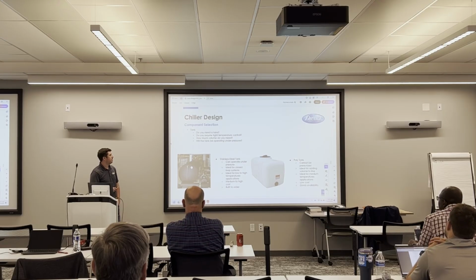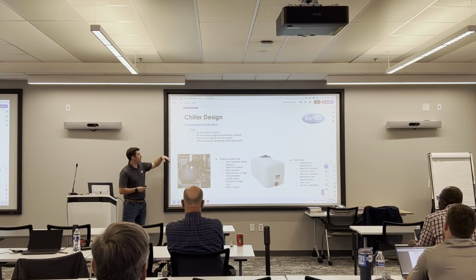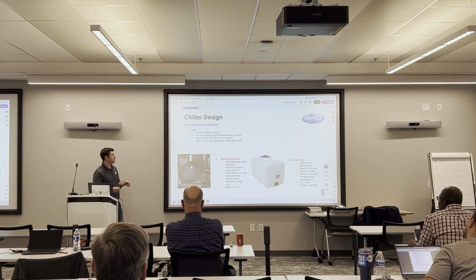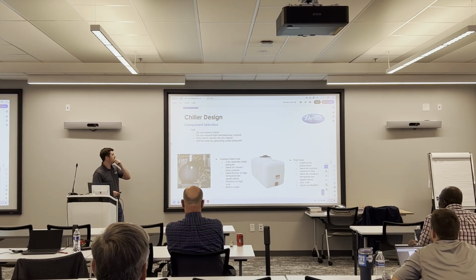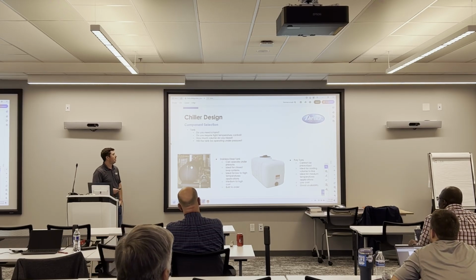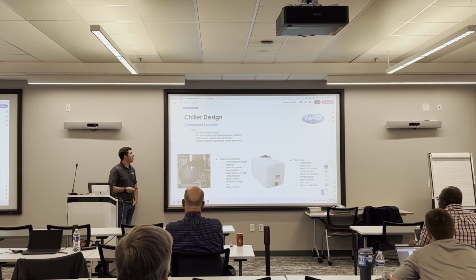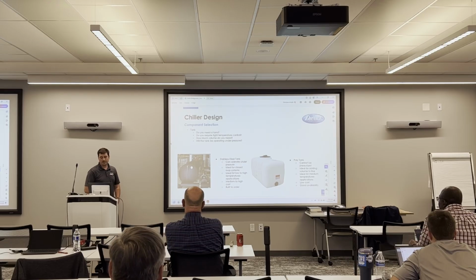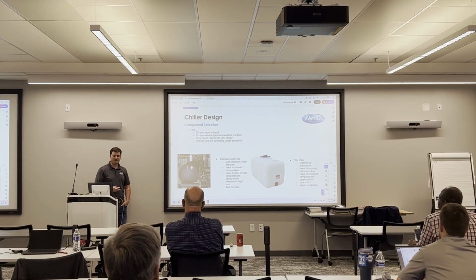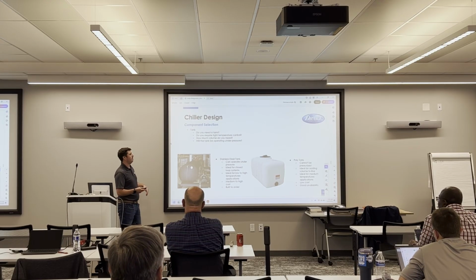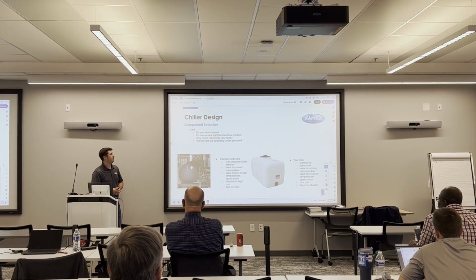So, just off the second bullet point here, do you require tight temperature control? If yes, we're probably going to set this tank up in a recirculation system, which we'll get to on the next slide. How much volume do you need? If they say 500 gallons, they're going to get a 500 gallon tank. But generally, you can quantify how big of a tank you need, at least on our end. A good rule of thumb is you figure out what your largest pump is that's drawing off that tank. Let's say it's 100 GPM, and I'll multiply that by 2, and I'll say I need about a 200 gallon tank. That's a general rule of thumb in our industry.